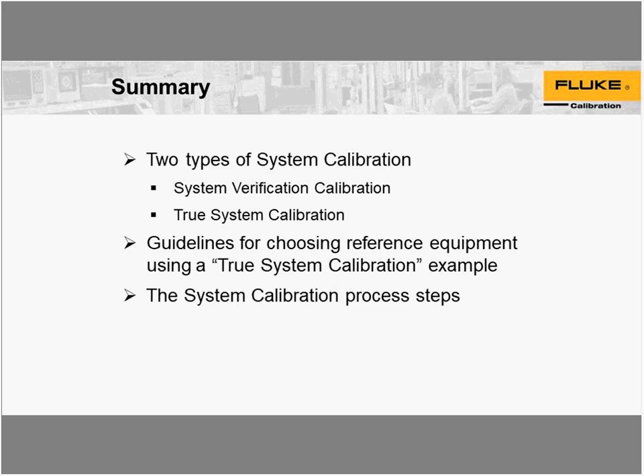Okay, good clarification. The next question, Roger, is a follow-up to the one about using predicted calculated temperature, saying the dry well's well-to-well conformancy specs and stability are being used in our uncertainty budget. Wouldn't the dry well then also be listed as a standard? That would be up to you. If you want to list it, that's okay. But you're still doing a comparison calibration. I would say that you shouldn't have to, unless you have not taken any uniformity data on your dry well.